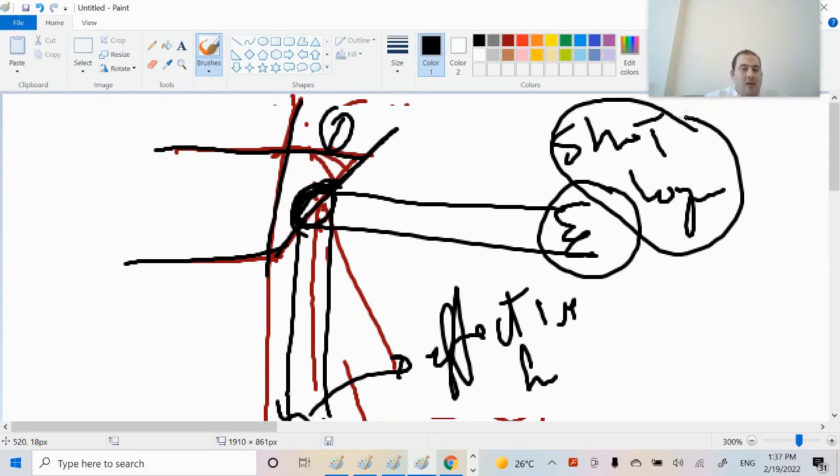In this case, you can perform examinations with very high parameters, such as high kV and high milliampere, like in CT and fluoroscopy, but ultimately at the expense of resolution, because the focusing you achieved was significantly diminished. When you decreased the focusing, you substantially lowered the resolution, but increased the tube rating of the machine, or enhanced the machine's ability to withstand high heat, as you distributed the electron beam over a larger area on the anode.